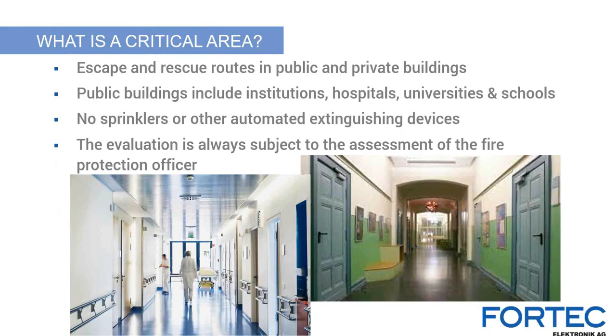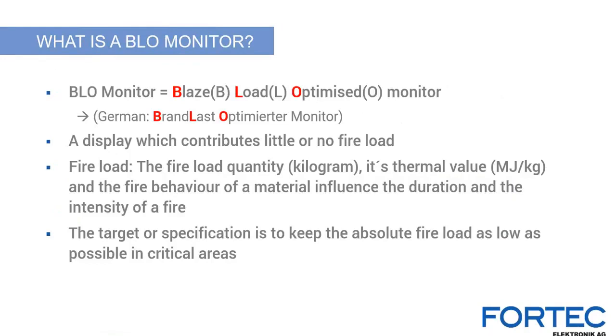A BLO monitor — Brandlast-optimiert, meaning fire load optimized monitor — is a display which contributes little or not at all to the fire load in case of a fire. This is achieved by avoiding materials with an increased fire load and by a construction that shields the electronics from the outside, allowing as little oxygen inside as possible. For example, a robust metal housing is used, the normal power cable is replaced with a fire protection cable, a ceramic fuse separates the monitor from the power supply in a fire event, and an optional extinguishing capsule is available inside the monitor.